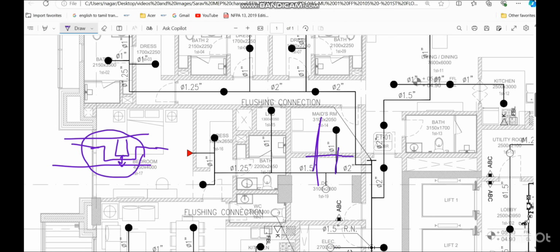So normally what people understand, this firefighting is a pressure line. We have the fire pump, it's a pressure line. So taken down and up, it will not create any issue. But NFPA 13 doesn't allow this one. As per NFPA 13, if you are taking up and down lines, this type of improper installation, you must provide the drain. So that is called as an auxiliary drain. You have to provide auxiliary drain wherever you are doing this type of mistake. So this is not allowed.